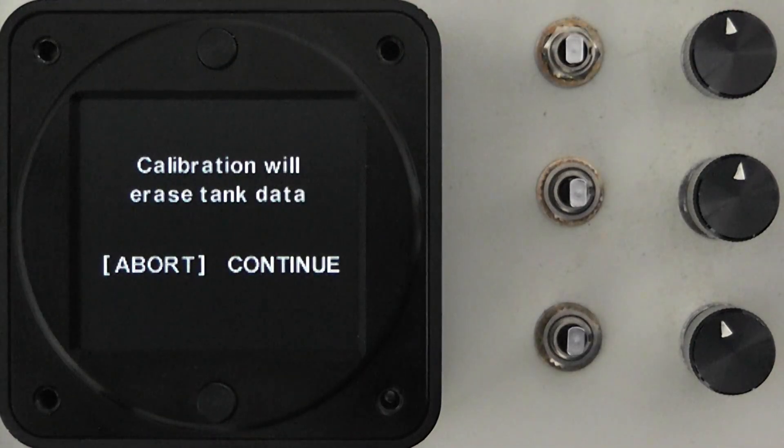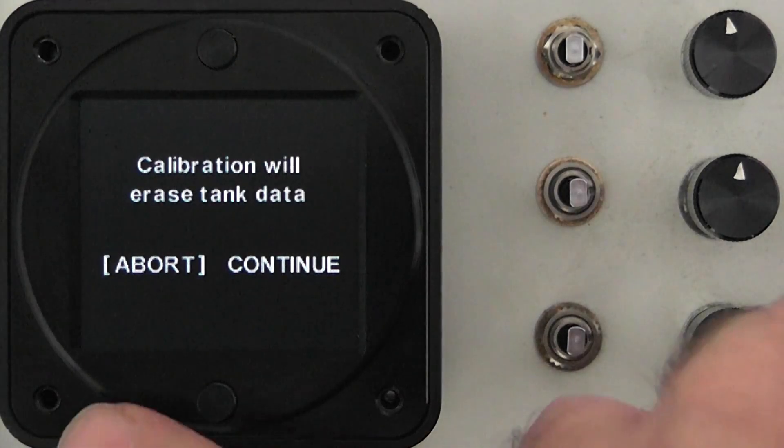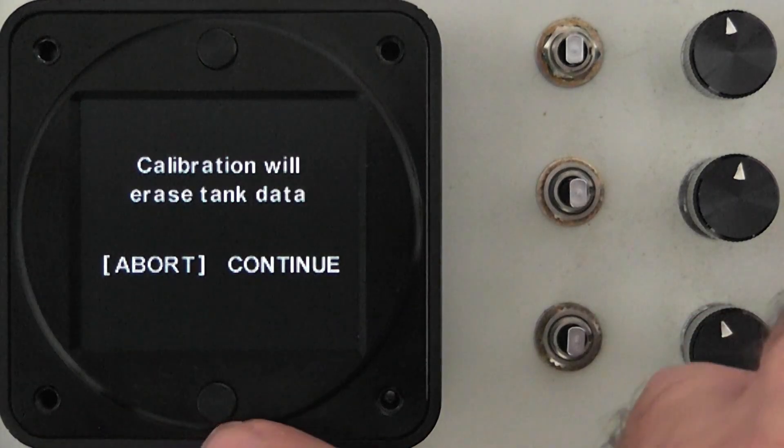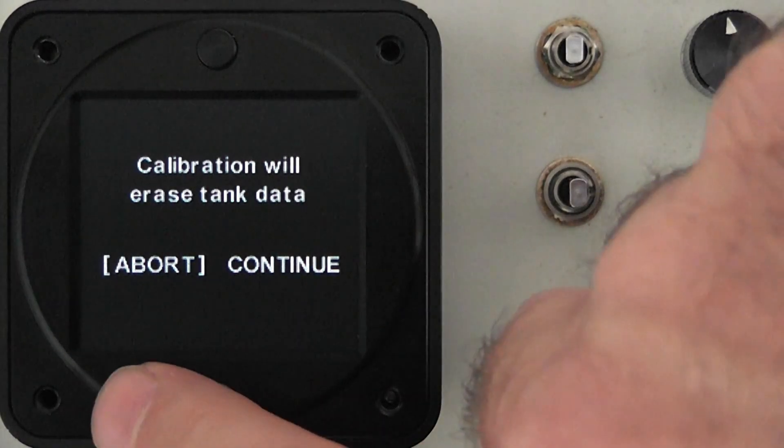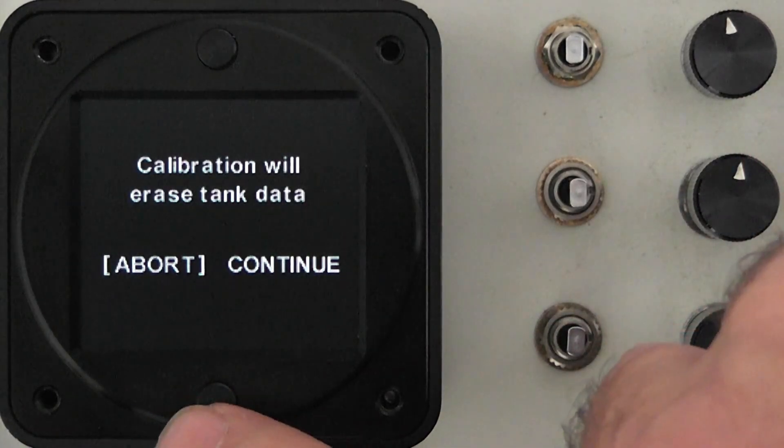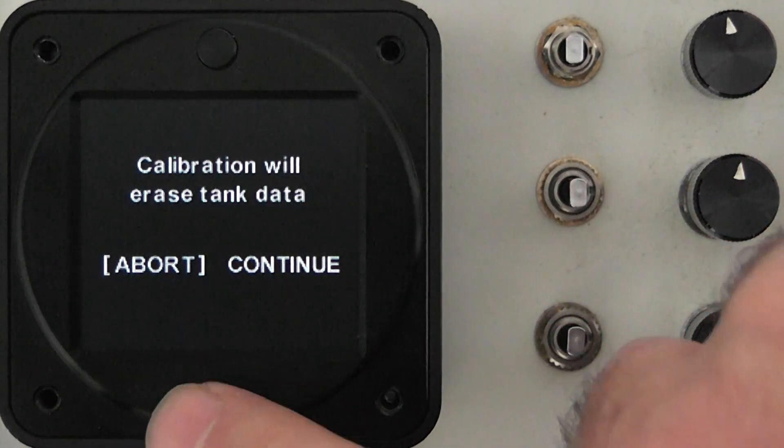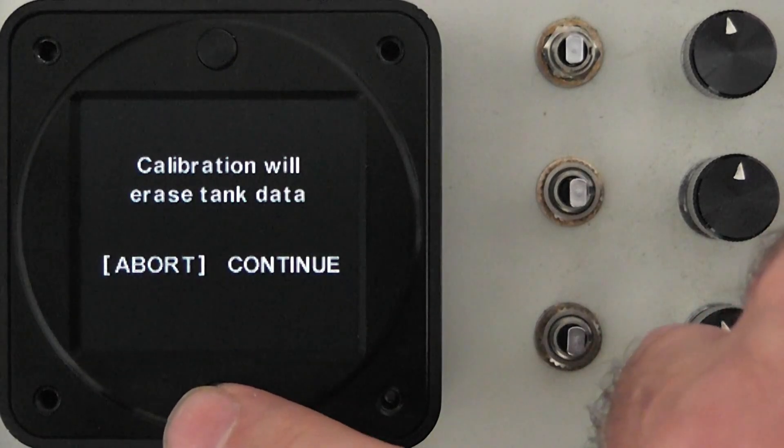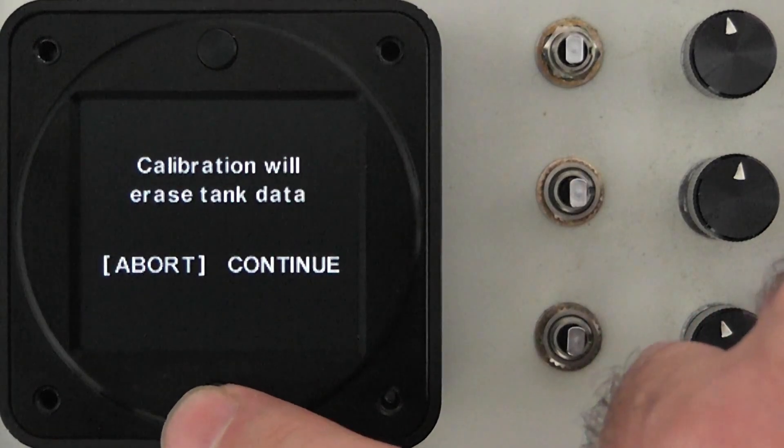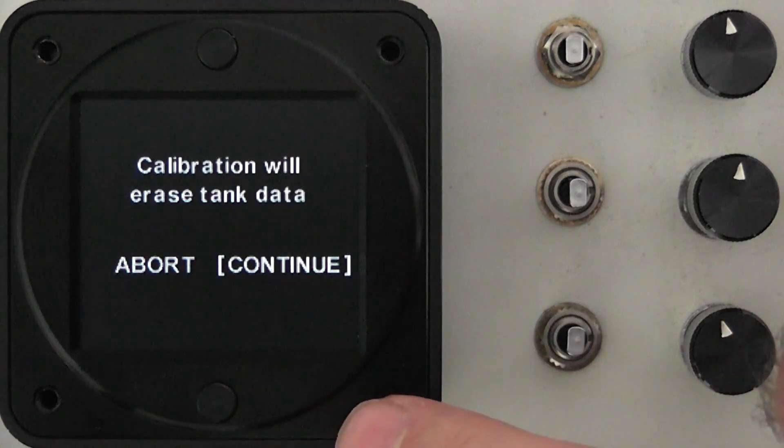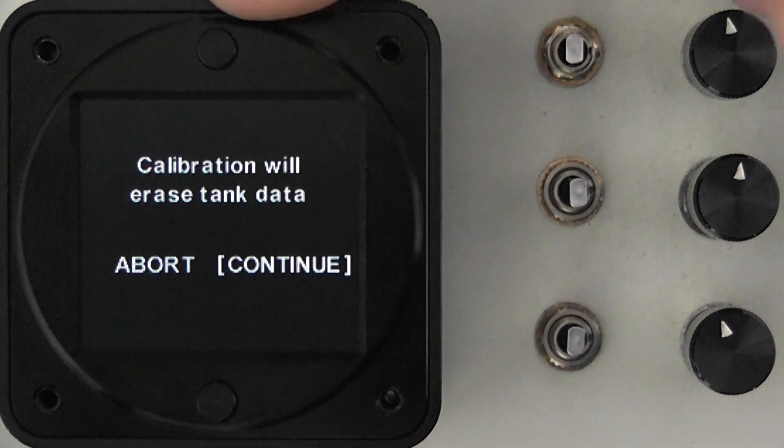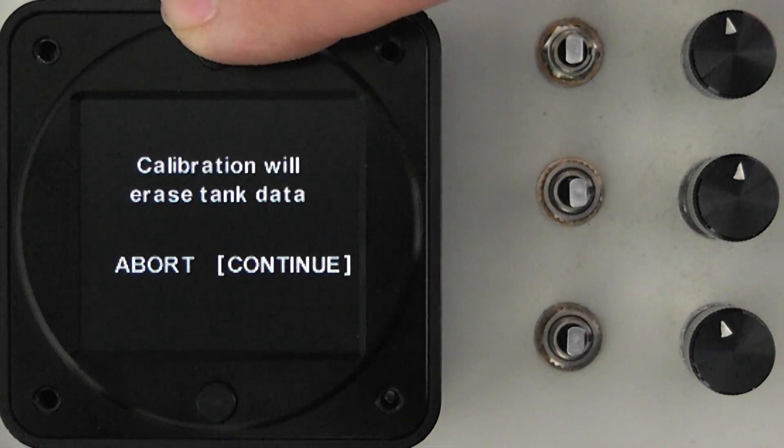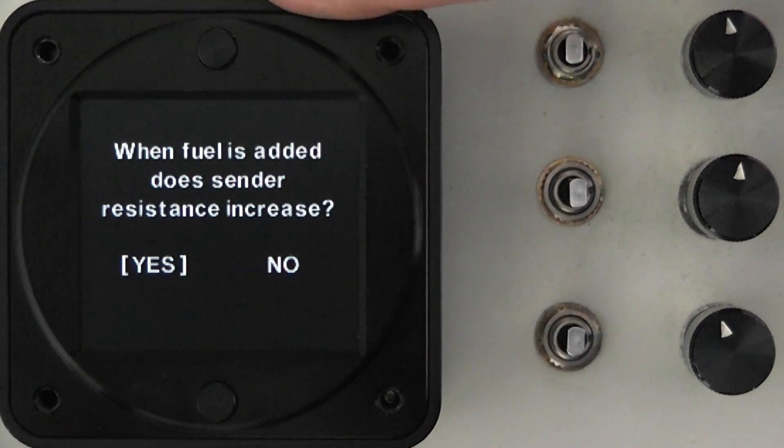You're given a warning that the calibration will erase the content of the tank data. Keep in mind that just entering the calibration procedure will not erase the data. It's only once you start calibrating a tank. By pressing continue at this point you haven't erased anything but the moment you start calibrating a tank any data that's there will be erased. So we'll choose continue in this case.